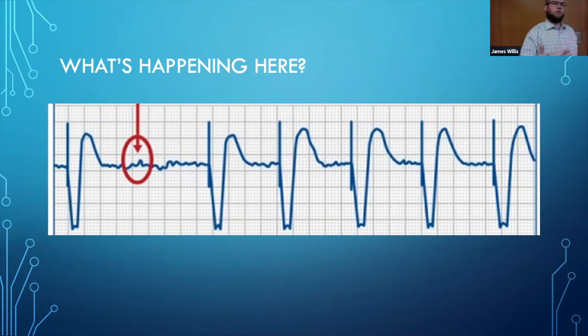We have things going on, and then suddenly we're not getting the right output. So we're calling this output failure. Basically, the rate on the ECG doesn't match the rate that we set on the box itself. There are several problems that can lead to this. There can be a lead failure, a generator failure, battery failure. If there's a dual pacemaker, so let's say this is a person that has a permanent pacemaker in place with an atrioventricular, it could be crosstalk inhibition. I'm not going to go into that today. It could also be something called oversensing, which we'll get to later.